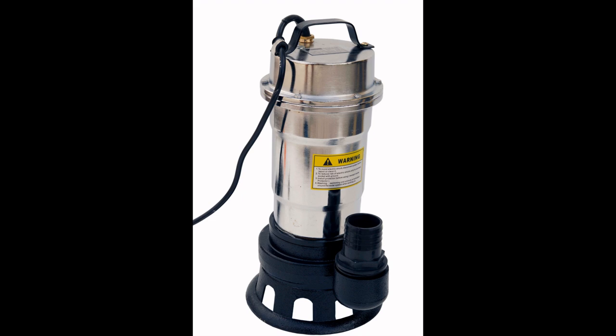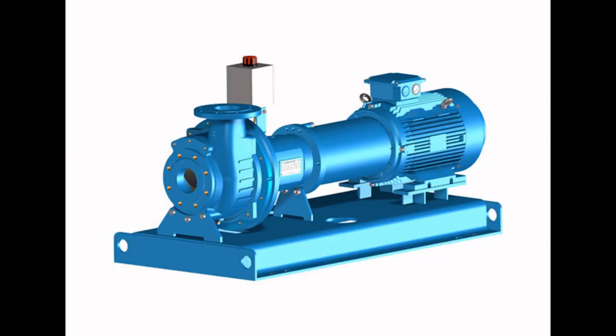In principle, to pump water 10 meters vertically, 10 meters water column height, we theoretically need 1 bar pressure. Thus, if the technical data sheet of the pump mentions that it has a maximum discharge height of 50 meters, this means that the pump develops a maximum pressure of 5 bars. Caution: the water flow at this maximum height will be practically zero.